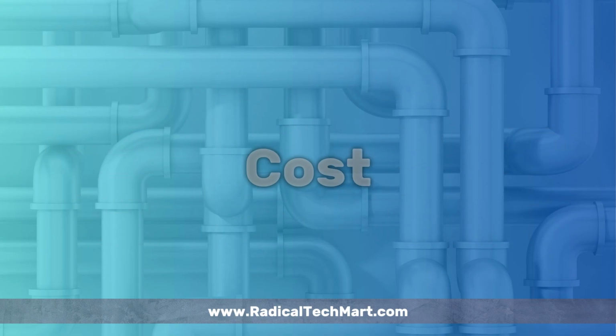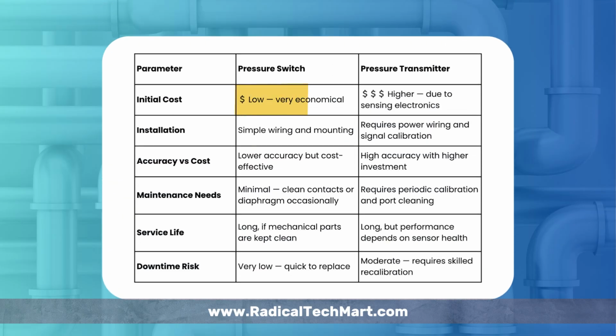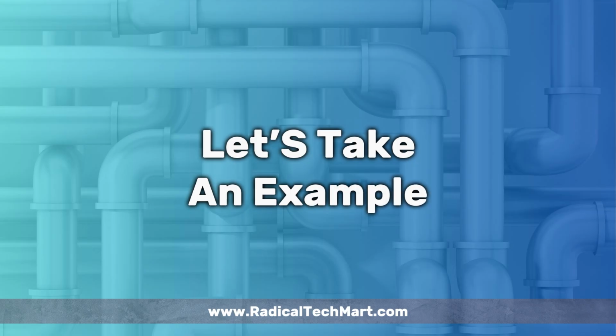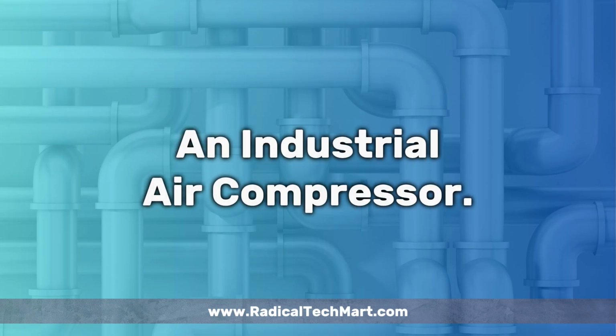In terms of cost, pressure switches are much more economical and simpler to install. Transmitters are more expensive, but they offer continuous monitoring, better accuracy, and remote data transmission. Maintenance-wise, switches require only occasional cleaning or contact checks, while transmitters require periodic calibration and clean sensing ports for stable performance. Let's take an example, an industrial air compressor.